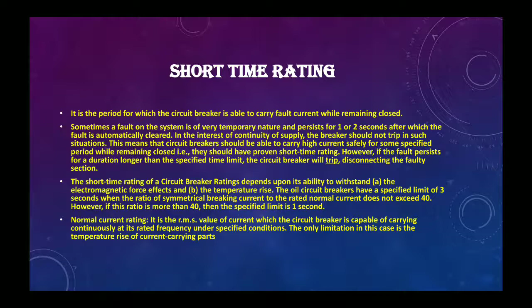Normal current rating. So what is normal current rating? It is the RMS value of current which the circuit breaker is capable of carrying continuously at its rated frequency under specified condition. The only limitation in this case is the temperature rise of current carrying parts. Due to the normal rating current, the I square R loss happens. So heat is produced in the current carrying parts.